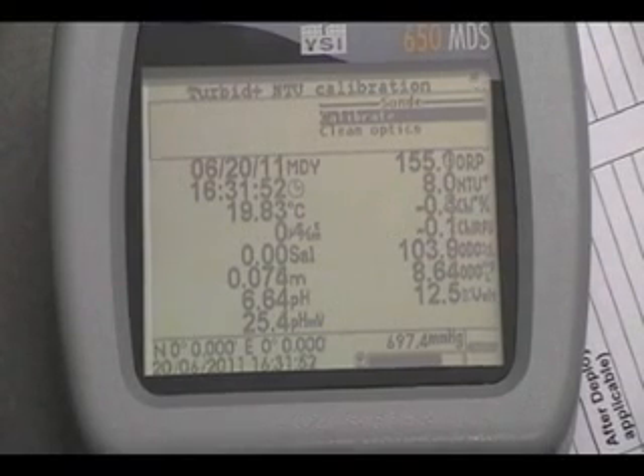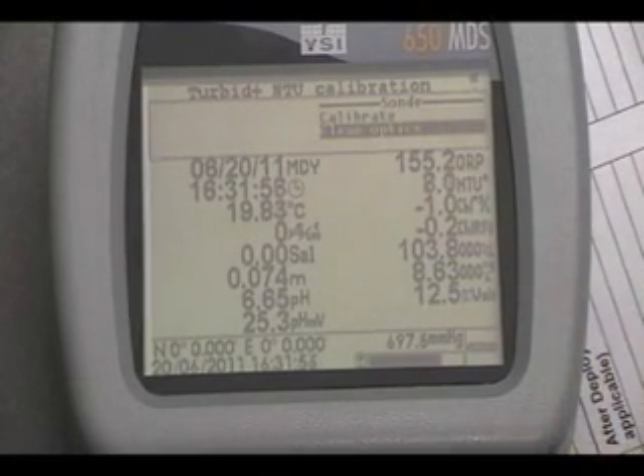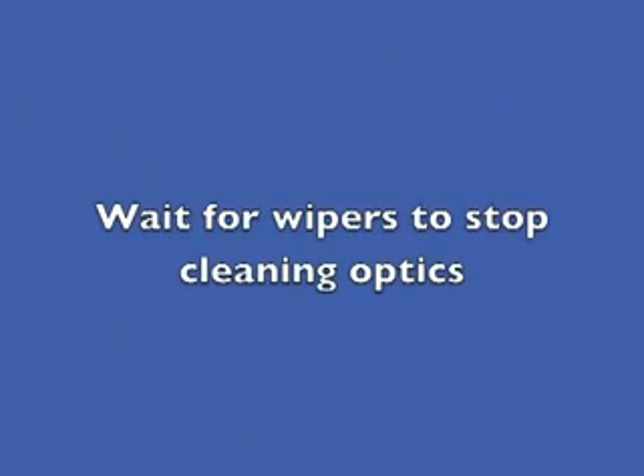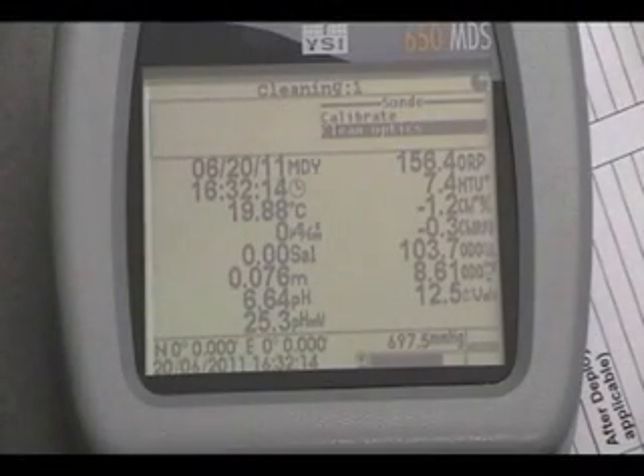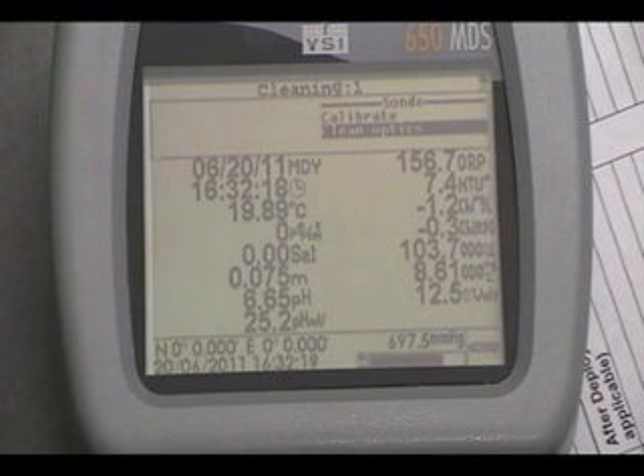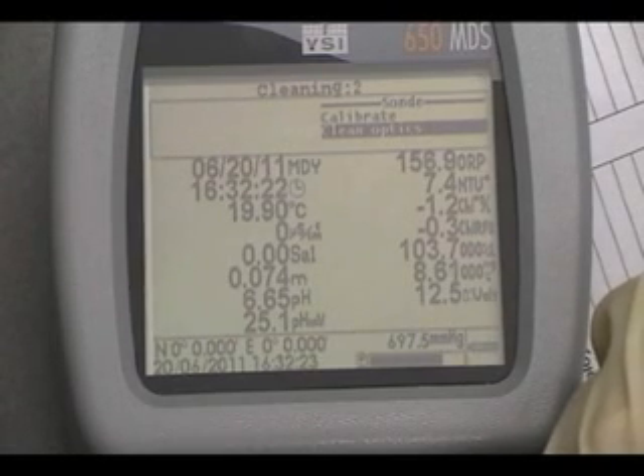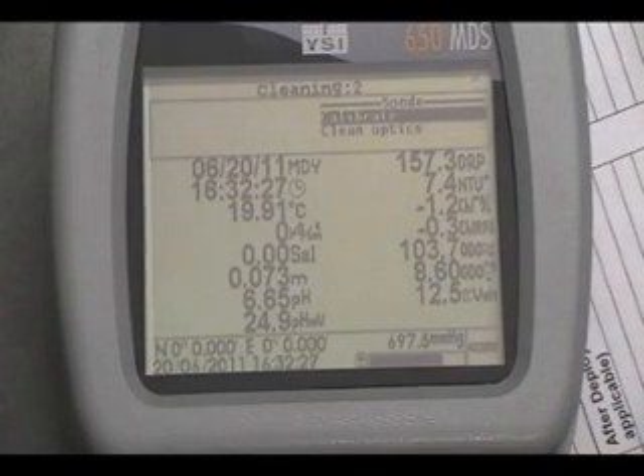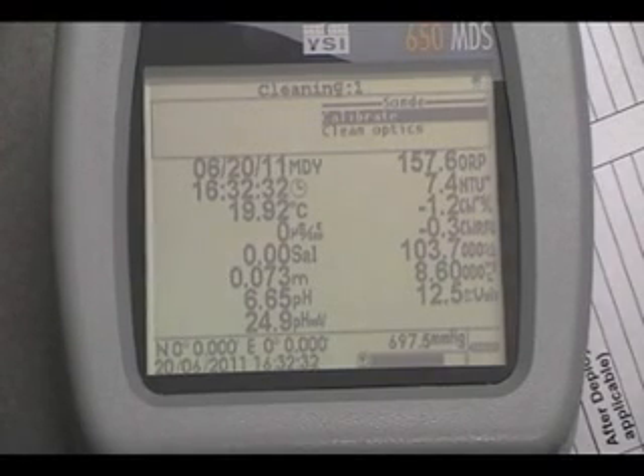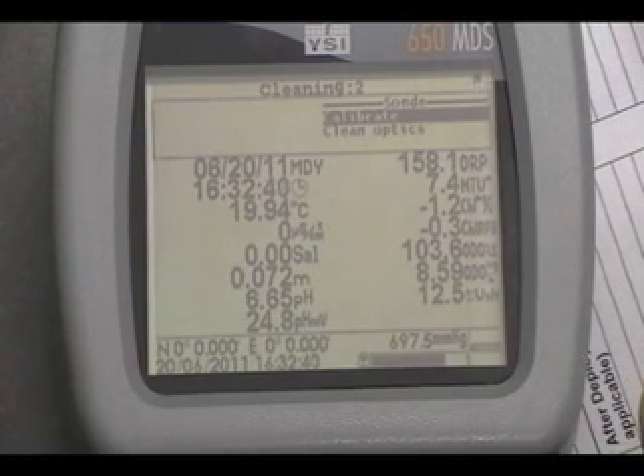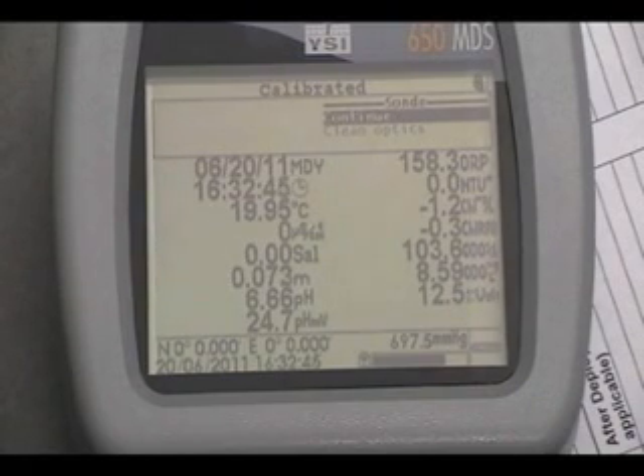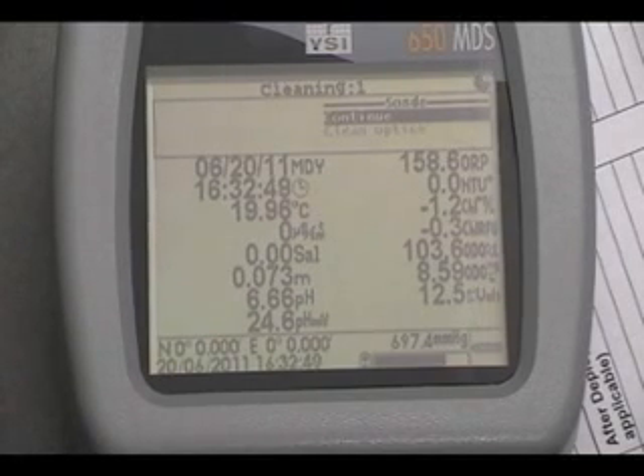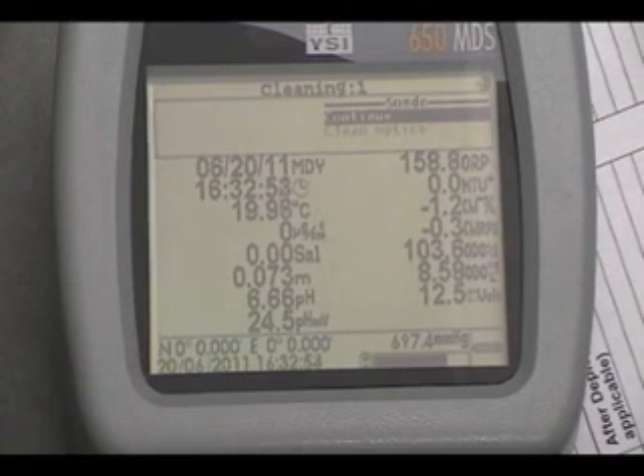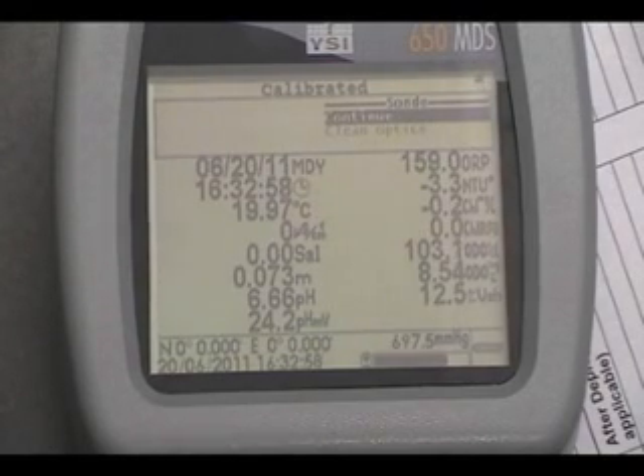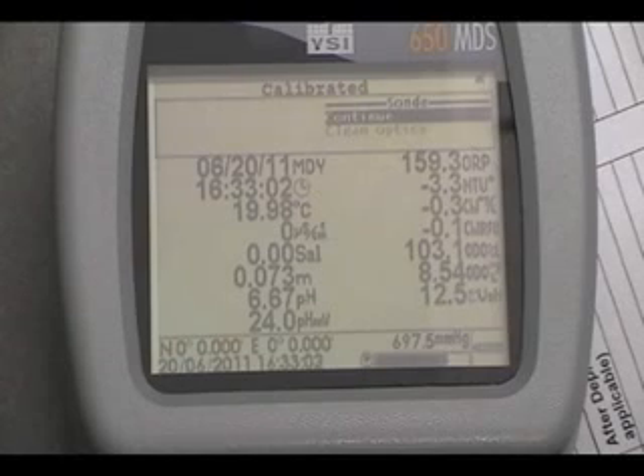Step 8. Activate the sensor wiper 1 to 2 times by pressing 3 Clean Optics. Step 9. When the readings have stabilized, record the pre-calibration turbidity reading for 0 NTU on the calibration worksheet. Step 10. Press Enter to confirm the first calibration and record the post-cal value for 0 NTU on the calibration worksheet. Step 11. Press Enter to continue.